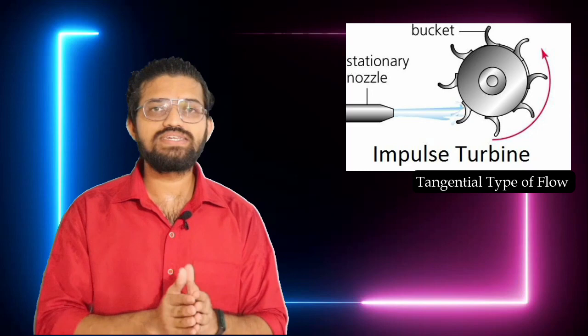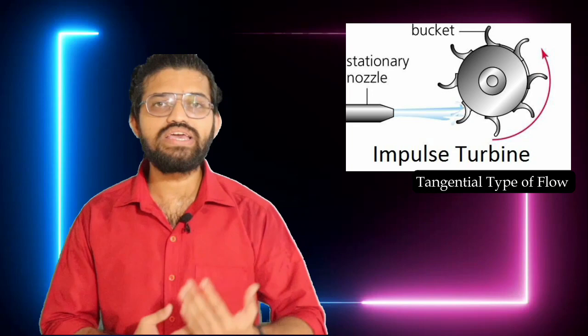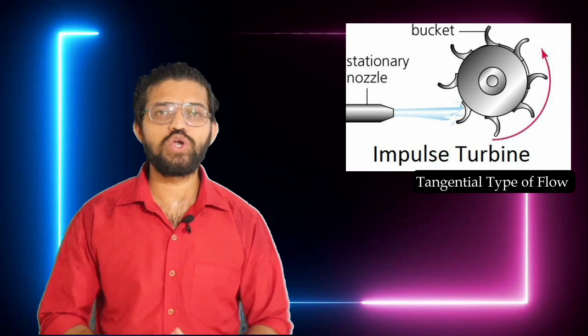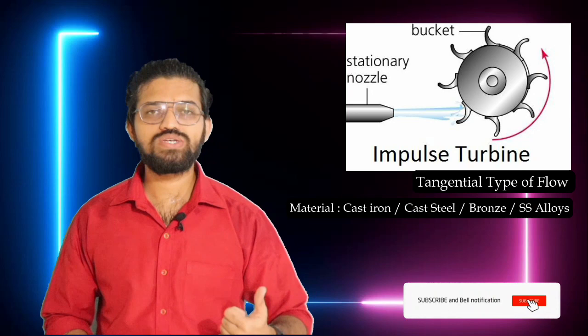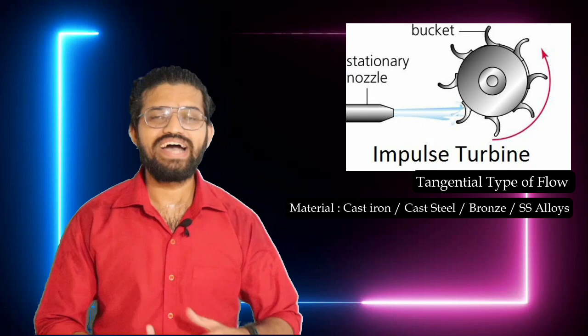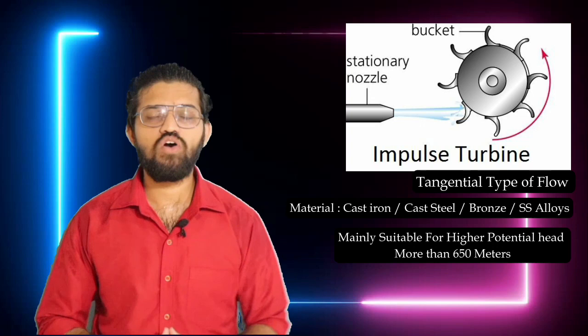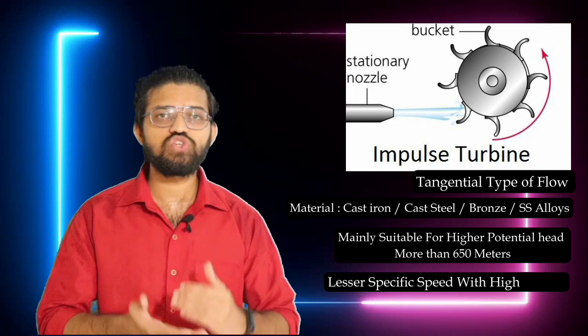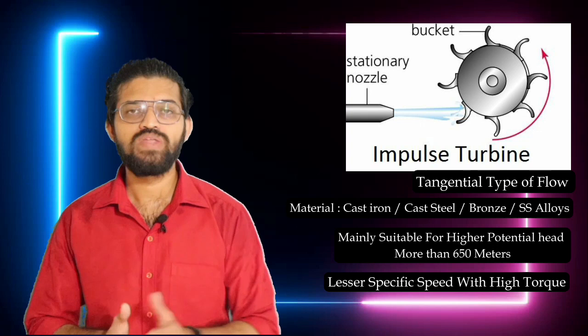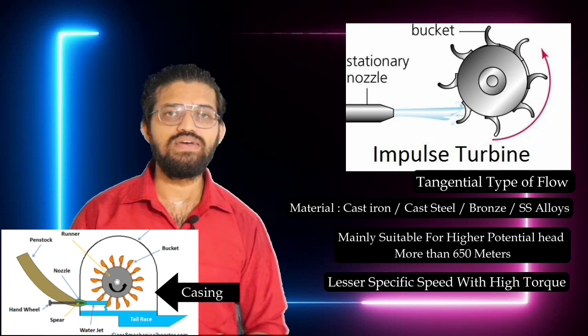This type of turbine is a tangential flow type, where the water jet strikes at the tangent of the Pelton wheel. The material of the Pelton wheel can be cast iron, cast steel, bronze, or various alloys. This turbine is mainly suited for higher potential heads — specifically, heads greater than 650 meters. The specific speed of the turbine is on the lower side, varying from 60 to 100.